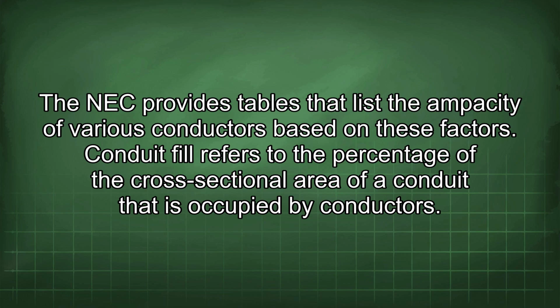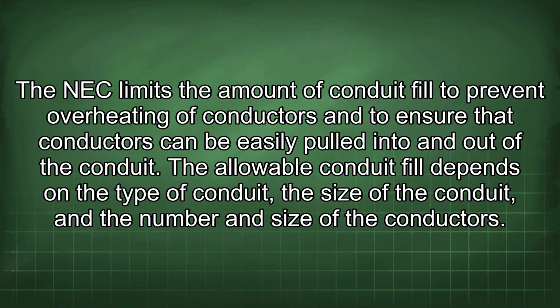Conduit fill refers to the percentage of the cross-sectional area of a conduit that is occupied by conductors. The NEC limits the amount of conduit fill to prevent overheating of conductors and to ensure that conductors can be easily pulled into and out of the conduit.